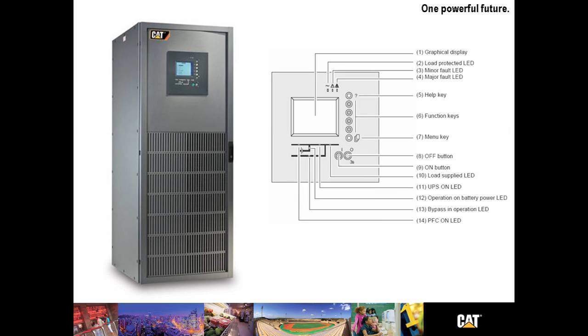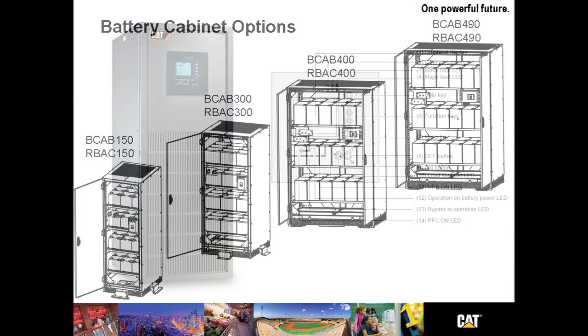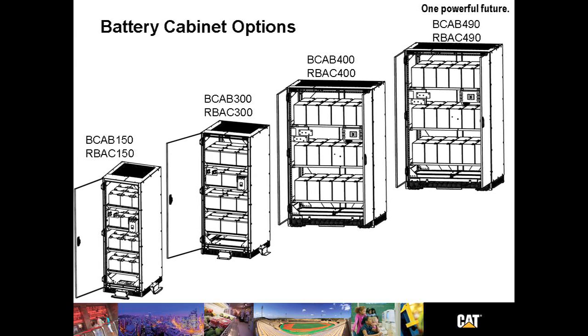Let's talk for a minute about communications. We talked about the HMI or Human Interface screen on the front of the UPS. The UPS can communicate in 18 different languages. It stores 2,500 time-stamped events, allows the operator to view statistical information about the UPS and its operation from the front screen. Communication interfaces include Modbus, RS-232, or RS-485 using the JBUS protocol, and SNMP.